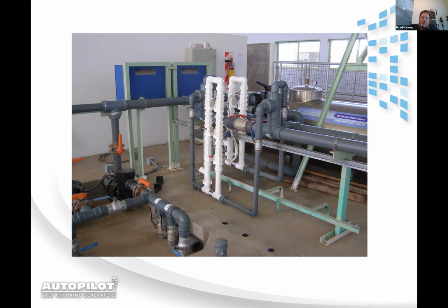We have pictured on the bypass a 5-pound check valve, but 5-pound check valves are pretty hard to get when you get into the larger plumbing. So ball valves or butterfly valves are typically used.